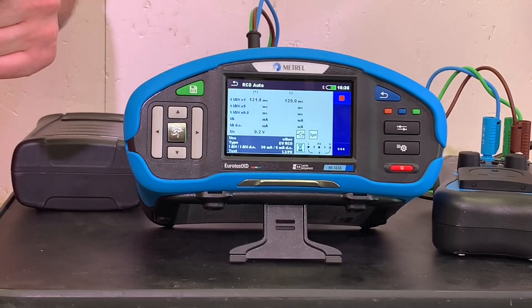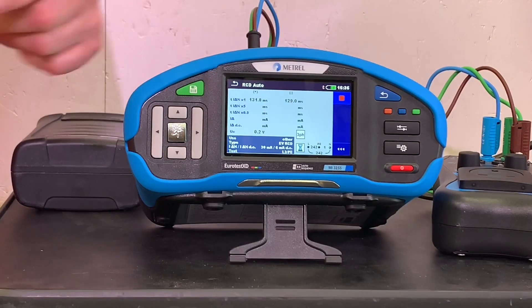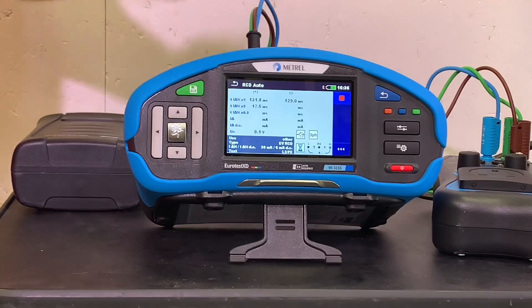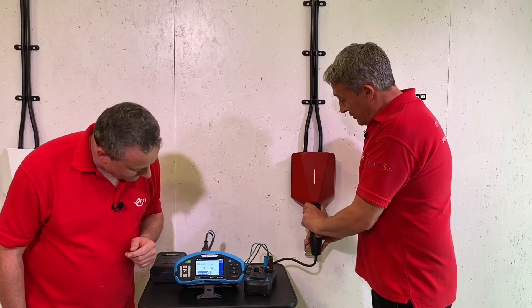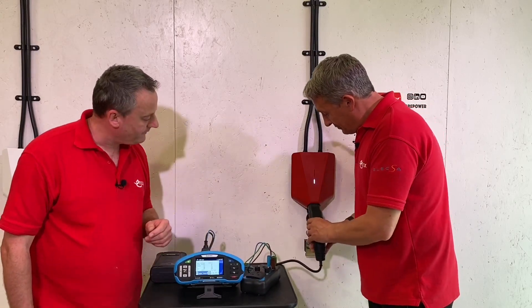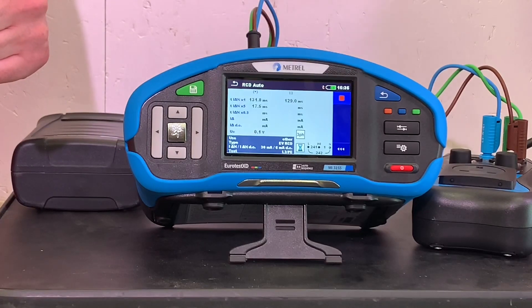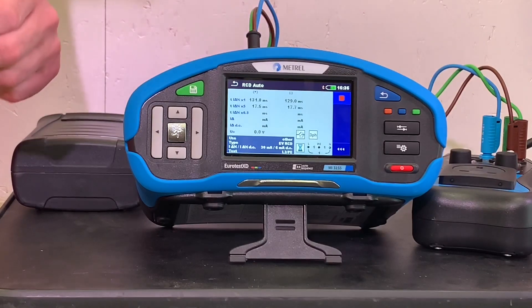This should be a quick trip time - less than 40 milliseconds. In the first half of the cycle, 17.5ms - reset again - and now in the negative half of the cycle we go again. This test is limited by how fast we can plug the lead in and out.